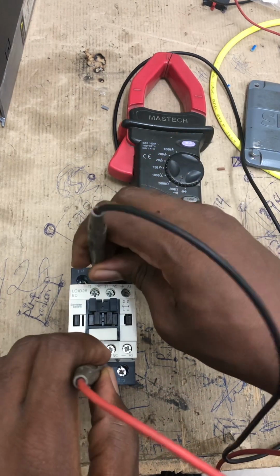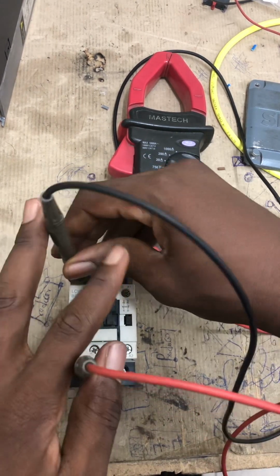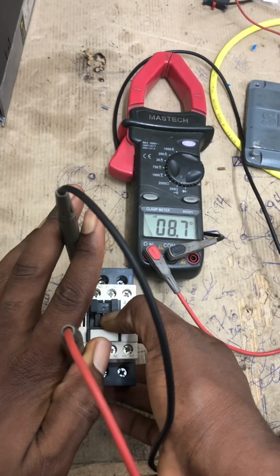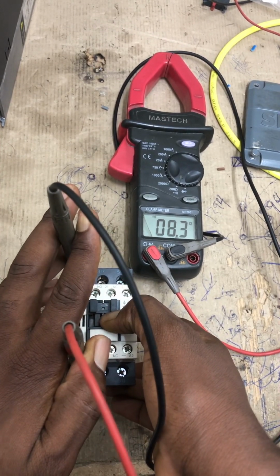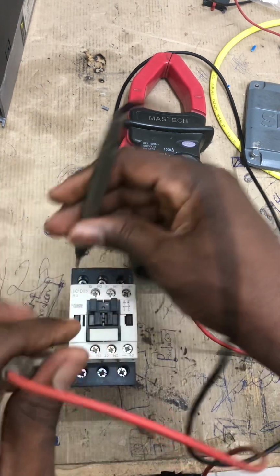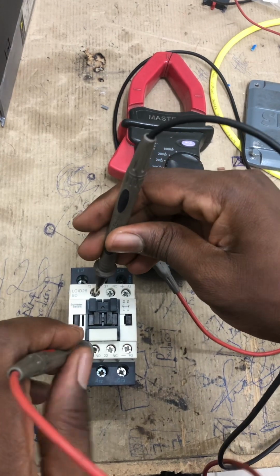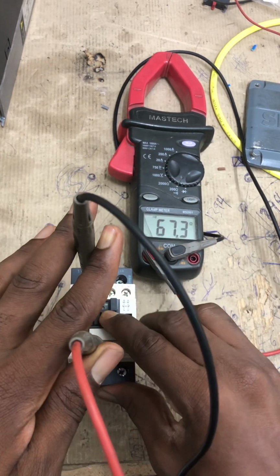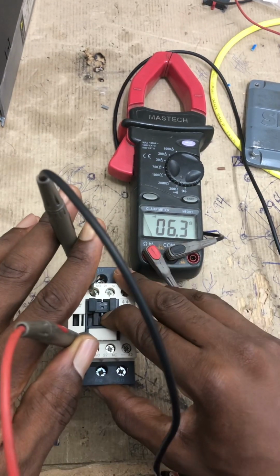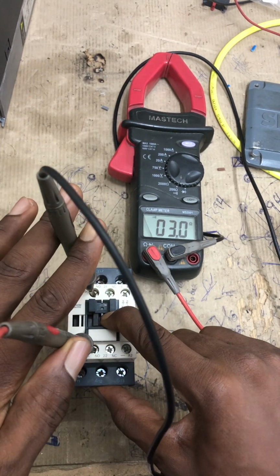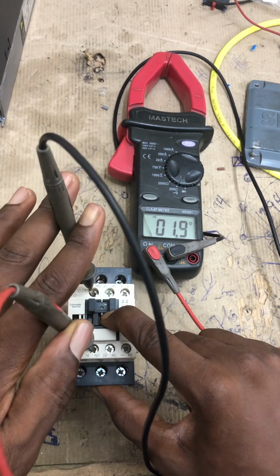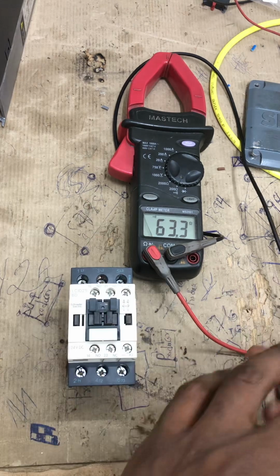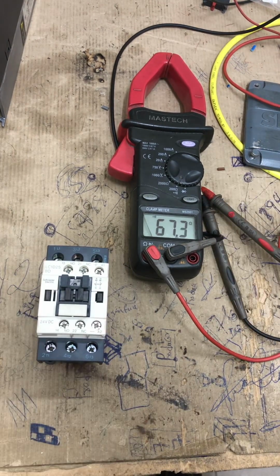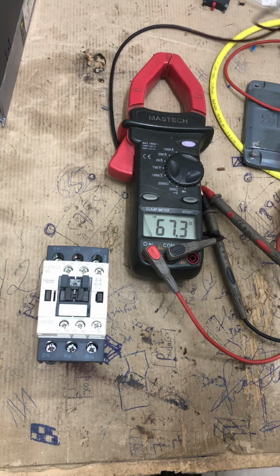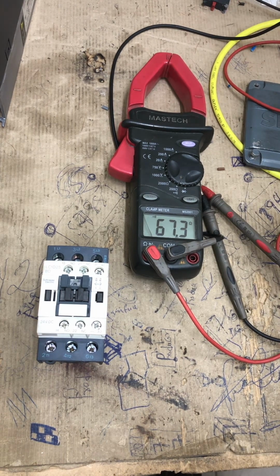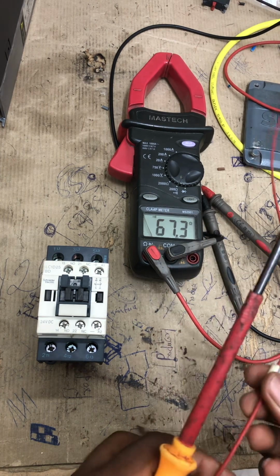You can manually test your contactor by pressing this side, and then there will be continuity. You can manually test by pressing, but it's not advisable to do that because of the high voltages. So this is a manual press. I'll try and energize the coil so that we'll test and see. To energize the coil, this is a 24 volt DC contactor.